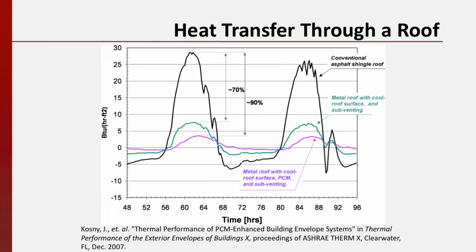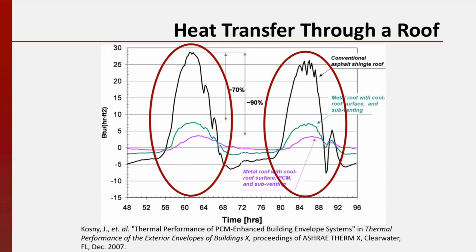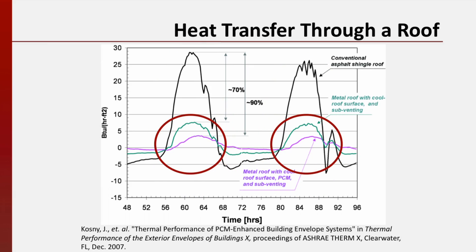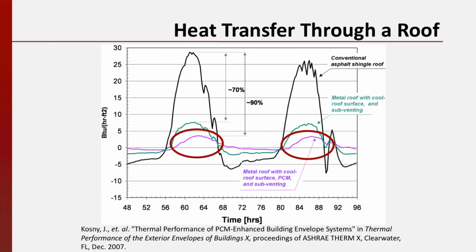Now let's look at the measured performance of a similar type of phase change insulation installed on a typical residential roof. The chart here shows heat transfer into a house on the vertical axis and time on the horizontal axis. The two large black peaks, which occur during two consecutive summer days, correspond to the large amount of heat transfer a conventional roof allows. The smaller green peaks show how changing the roof surface material and venting the attic significantly lower heat transfer into a home by approximately 70%. The purple curve shows that if phase change insulation is used in addition to these roof modifications, we can reduce the required cooling energy by 90%.